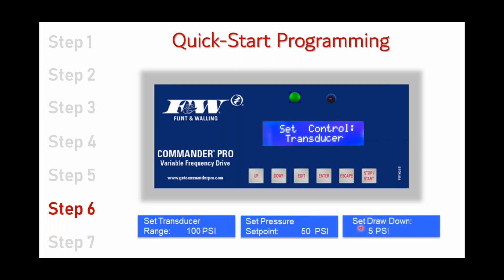And then the third submenu that's going to pop up, it's going to ask you to set your drawdown. It's going to come out at a factory default of 5 psi. Basically what we're saying there when we talk about drawdown is how far below that set point pressure do you want the system pressure to drop before this system comes on, before the drive powers up and brings water. Well, that drawdown is 5 psi. Most people cannot determine a 5 psi drop in pressure. They can determine a 20 psi drop in pressure, but a 5, not so much.